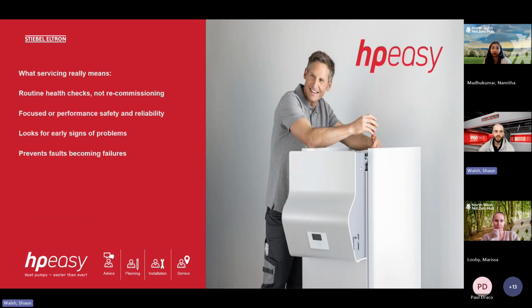So I'm just going to quickly move on to this next slide. In reality, when we're looking at servicing, what it means for you if you go to site is basically a routine health check for the heat pump to make sure that it's running as it's intended. So it's not a full recommissioning of the system. It's checking that the current parameters still match the initial commissioning parameters. As I'm sure you all know, people change things over time. So we just need to check that the parameters that are set are the same as the original commissioning parameters, right? And it should focus more on performance, safety, and reliability.